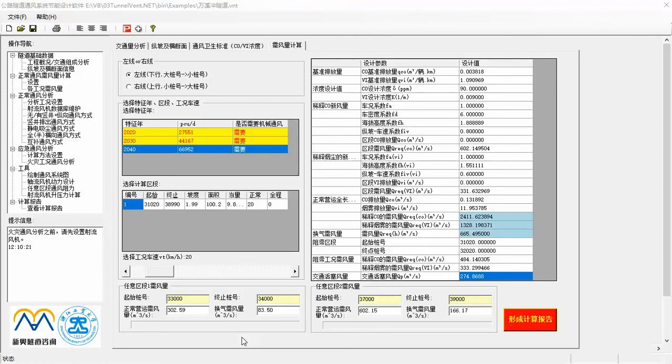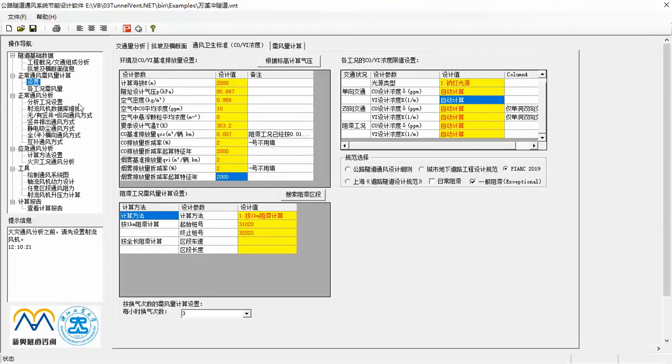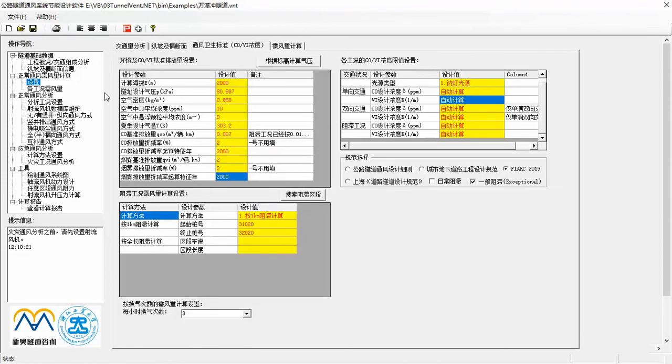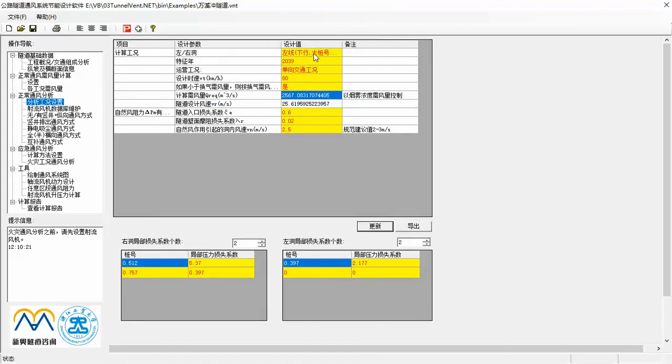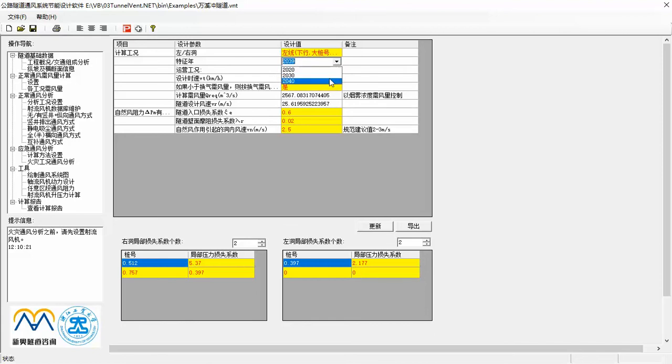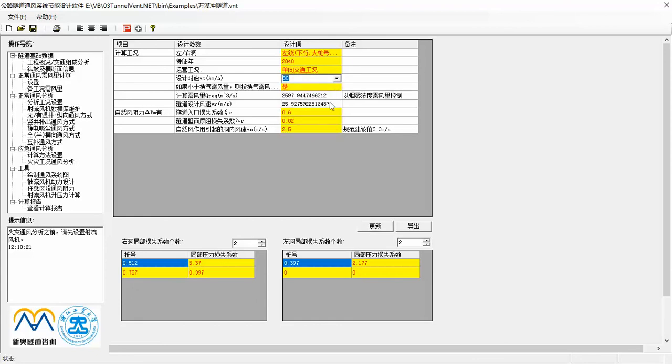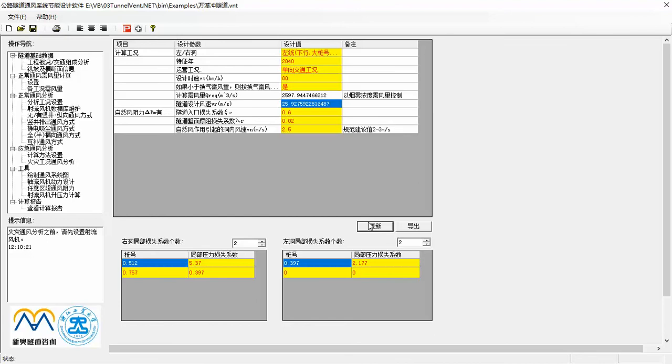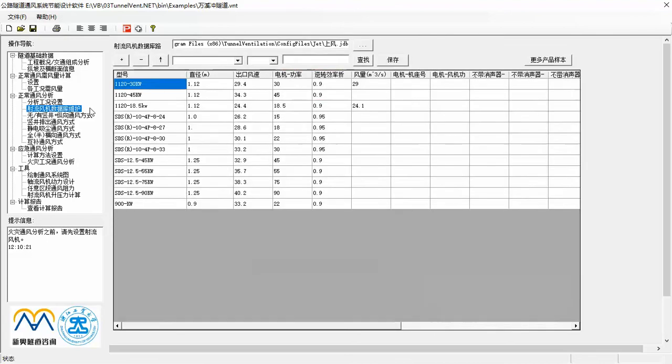Then, let's go to the third step to analyze normal operation. First, select the tube, a future year, a traffic condition you are going to analyze. Here you can also define friction coefficient along the tube, resistance coefficient at entrance and exit portals, as well as local resistance coefficient along the tube. Secondly, you can link a jet fan database, which you can get from jet fan manufacturing to the software. The jet fan types listed in the table are ready to be selected in later analysis.